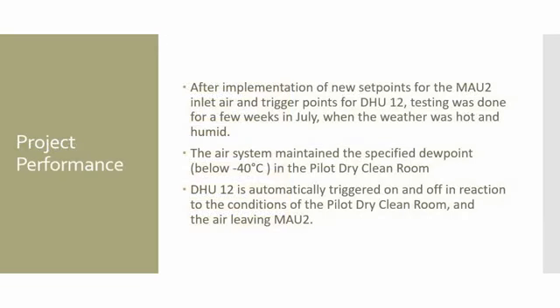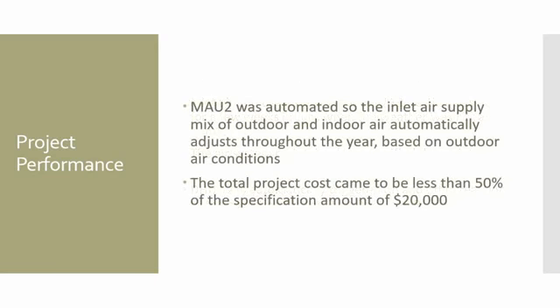The improvements made throughout this project met the deliverables set at the beginning. First, and most importantly, the system can maintain a dew point below -40 degrees Fahrenheit throughout the whole year with no human involvement. The DHU12 will trigger on and off based on the dry clean room dew point and the dew point of the air leaving MAU2. MAU2 is automated so the inlet air supply can be switched throughout the year. Finally, the project cost was 50% less than the planned amount.